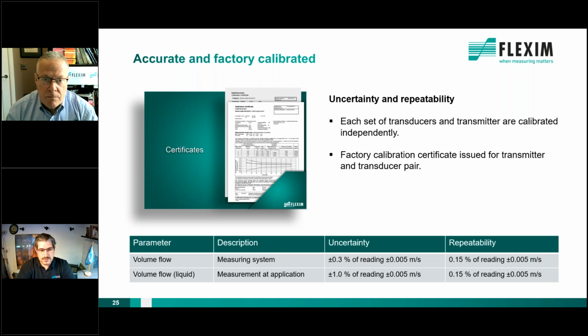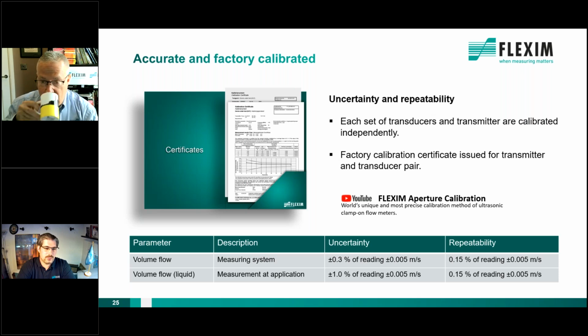In the end, what we have is a 0.3% measuring system accuracy on the calibration, and for the actual field application, we specify an uncertainty of 1%. So this is what you get: 1% accuracy in the field when you put our transducers on any given pipe. If you'd like to learn more, you can visit our YouTube channel and see how this aperture calibration works. This is quite interesting. Also, what we're going to introduce is the ISO 17025 accreditation, the standard for an approved calibration laboratory, which has been delayed due to the pandemic, but which will hopefully come by the end of this year.